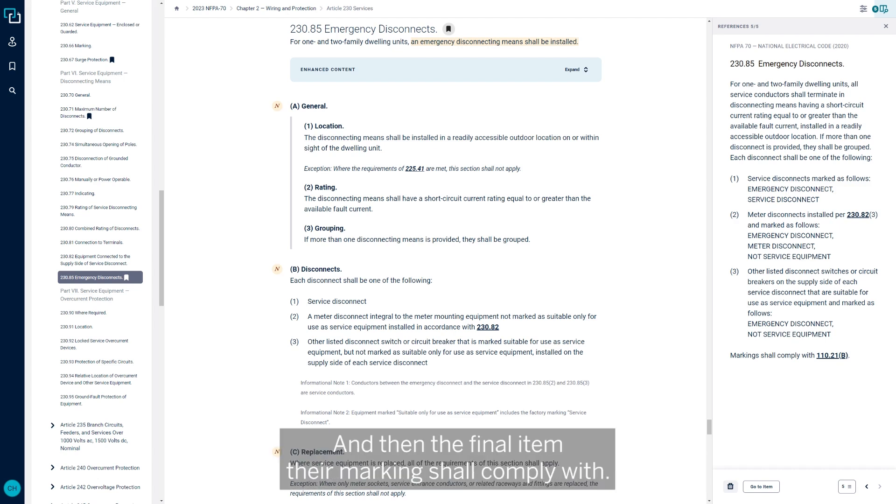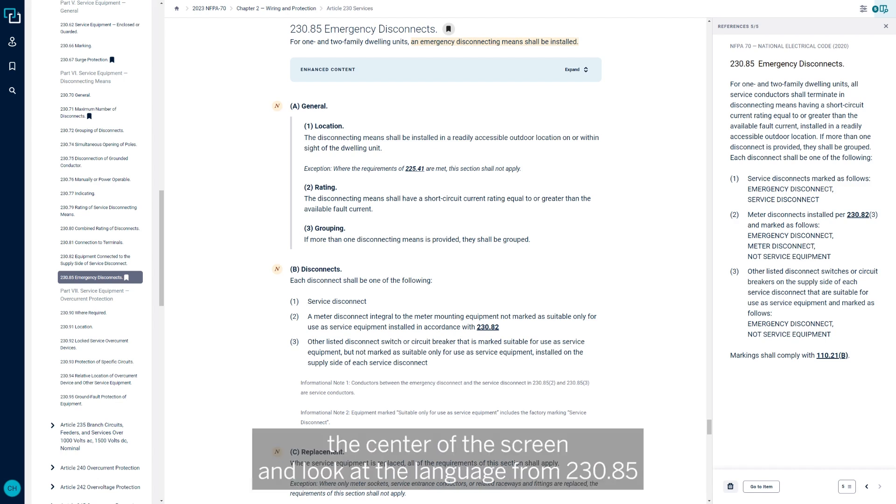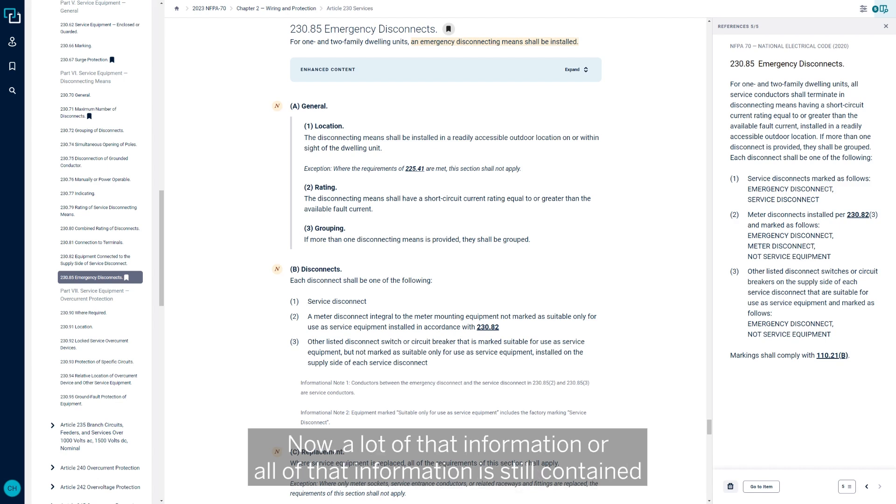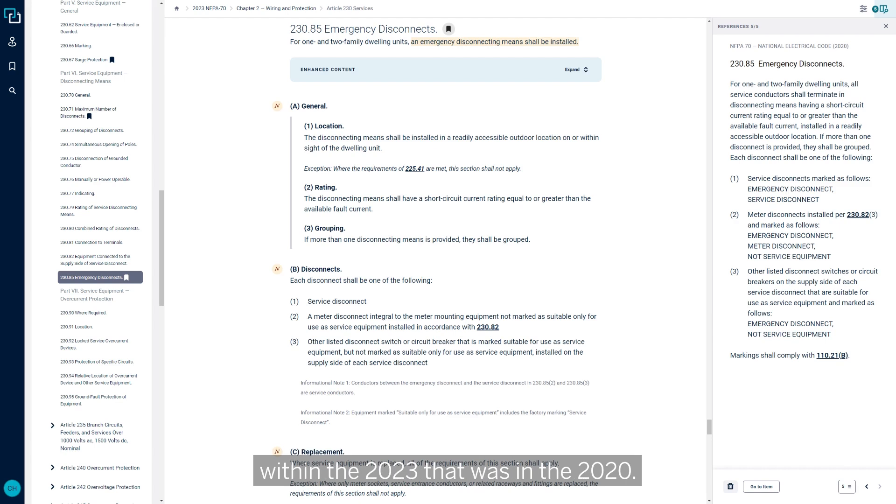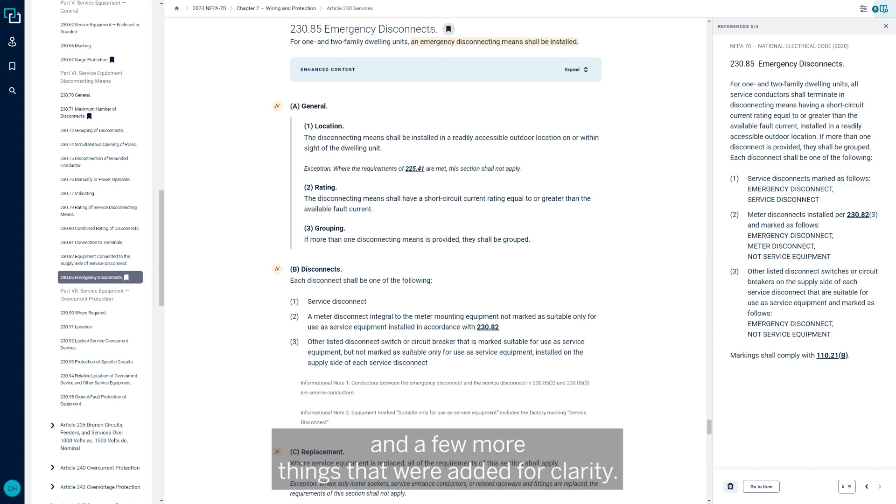All service conductors must terminate in a disconnect means having a short circuit current rating equal or greater to the available fault current installed in a readily accessible outdoor location. If more than one disconnect is provided, they must be grouped, and each disconnect shall be one of the following. Markings shall comply with 110-21-B.